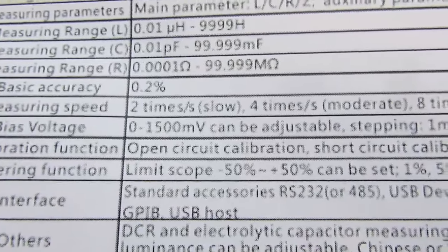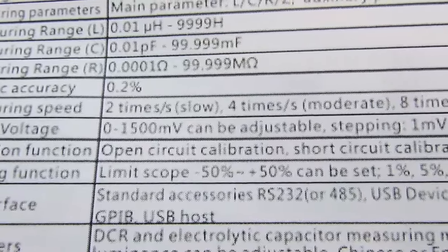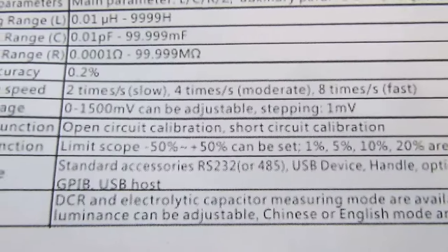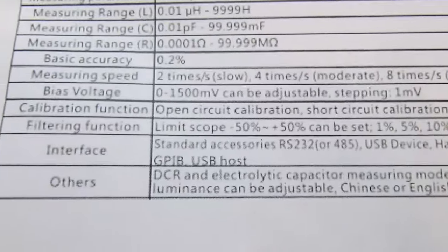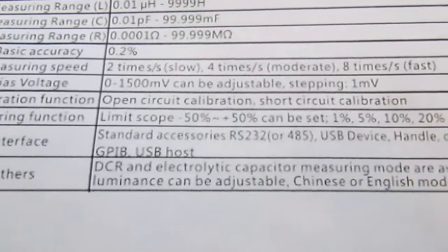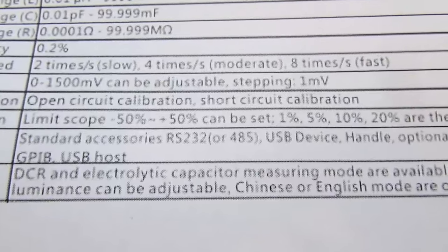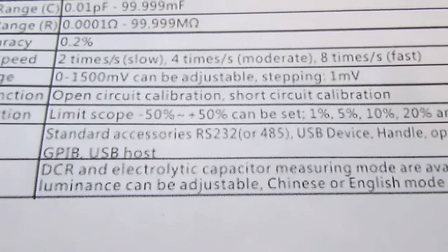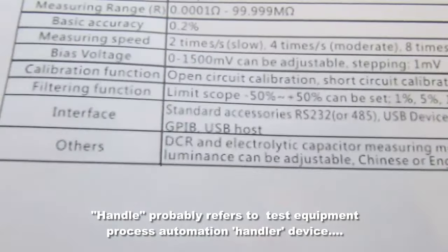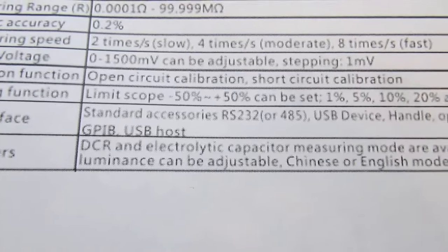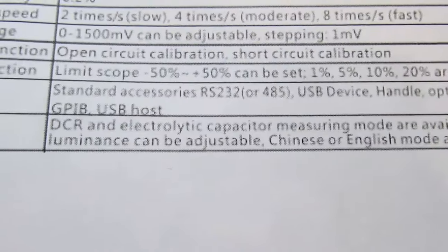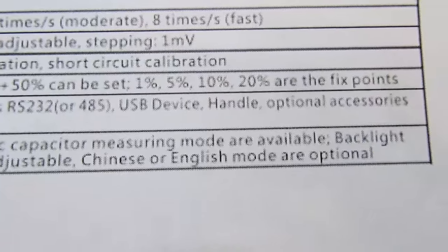It can have a bias voltage of 0 to 1500 millivolts, adjustable or stepping in 1 millivolt increments. Open circuit calibration, short circuit calibration. It has various interfaces like RS-232 or RS-485, USB, GPIB. It can measure DCR and electrolytic capacitor. Backlight luminance can be adjustable. Chinese or English mode are optional.